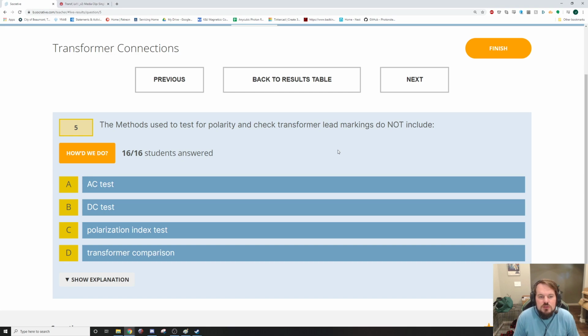The methods used to test for polarity and check transformer lead markings do not include the polarization index test. That's not a thing, it won't be found in the book. You can find the AC test, the DC test, and transformer comparison on page 74, under polarity test methods, all listed there.